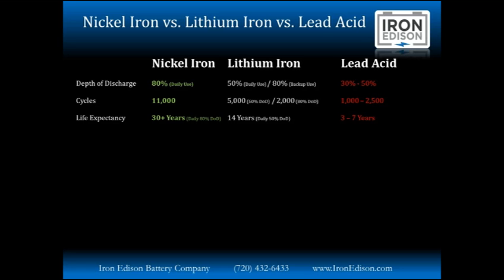Lithium iron batteries, like a lot of other battery chemistries out there, the deeper you discharge it, the shorter the life expectancy you're going to see. We've crunched the numbers and found if you're in a daily discharge situation, an off-grid solar home or something like that, where you're going to be cycling it every single day, 50% depth of discharge is the financial sweet spot. You're going to get a 5,000 cycle life expectancy, cycling it daily, 14 years of life out of a lithium iron battery.